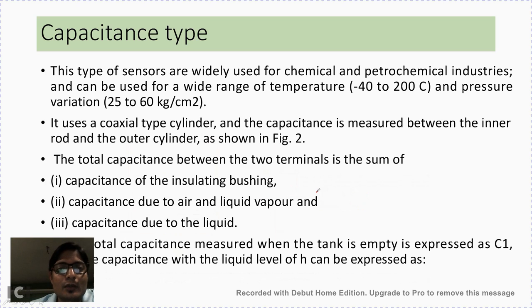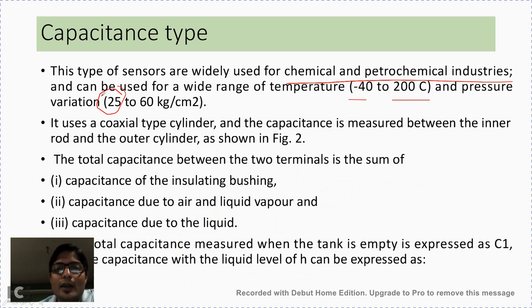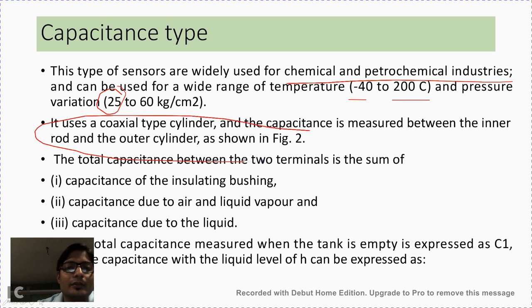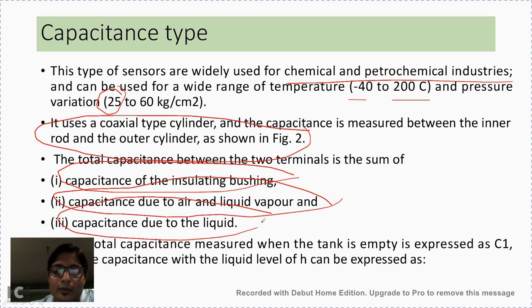Next is capacitance type. These sensors are widely used for chemical and petrochemical industries and can be used for a wide range of temperatures — from minus 40°C to 200°C — and pressures ranging from 25 to 60 kg per centimeter square. It uses a coaxial-type cylinder and the capacitance is measured between the inner rod and the outer cylinder as shown in the figure. The total capacitance at the two terminals is the sum of the capacitance of the insulating bushing, capacitance of the air and liquid vapor, and the capacitance due to the liquid, which directly indicates the level.